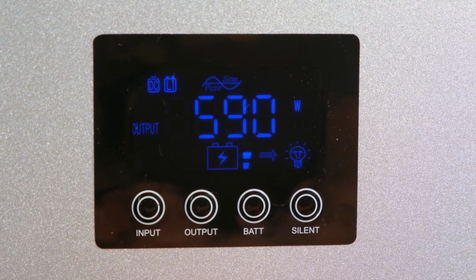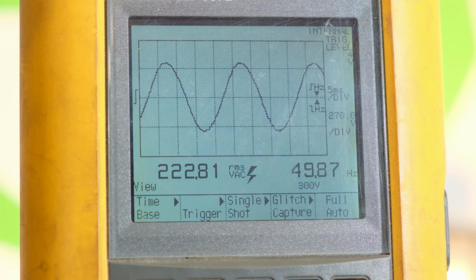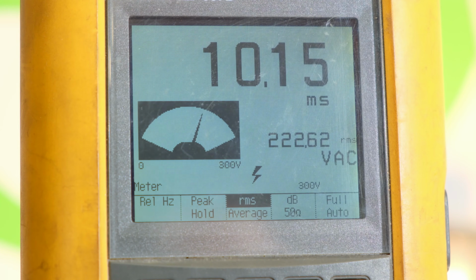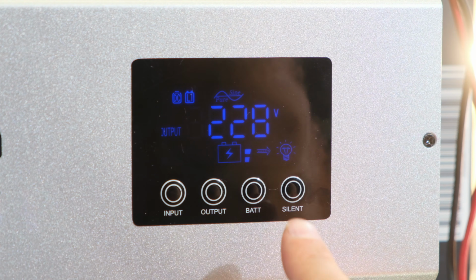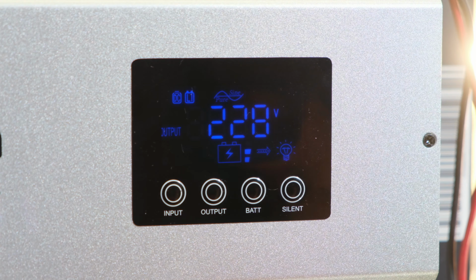Right, I'm at 590 watts. Let's have a look at the waveform. And the voltage has dropped down to just under 223 volts. The frequency is stable. The waveform looks good. The duty cycle is fair. On the unit, it says the voltage is 228 volts, although my meter says 223 volts. I'm going to leave it on for 10 minutes and see what happens.